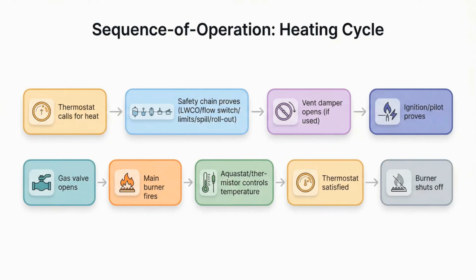Operational checks are essentially proving the sequence of events. Raise and lower the thermostat to force a call for heat, and then satisfaction. Verify ignition and main burner operation. Then test safety shutdowns like low water cutoff and flow switch. These must stop fuel if there's low water or no flow. Finally, verify the temperature control. An aquastat or thermistor-based control actually cycles the burner and then gets set back to the desired temperature.